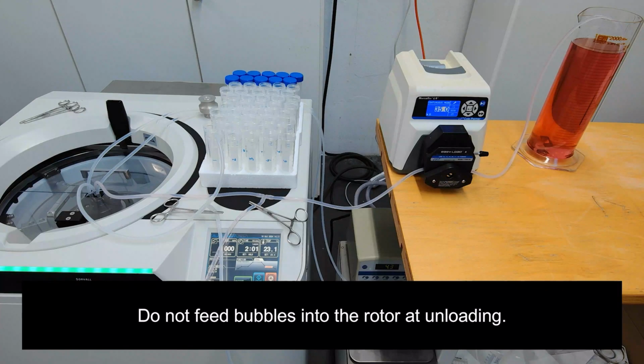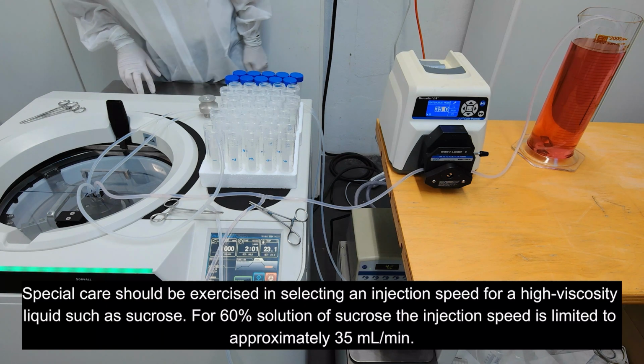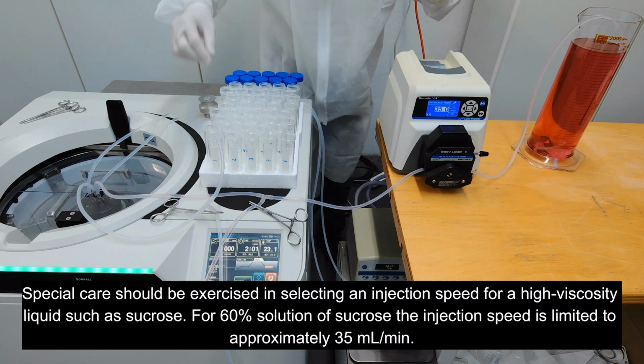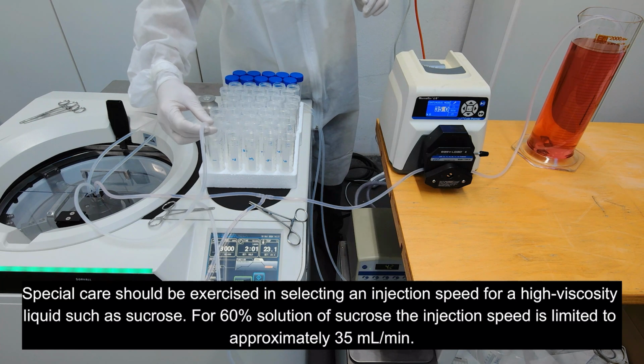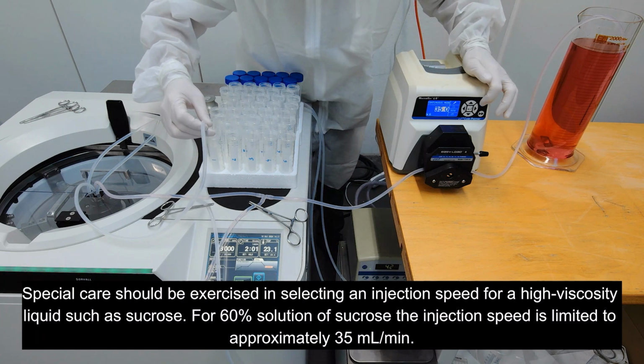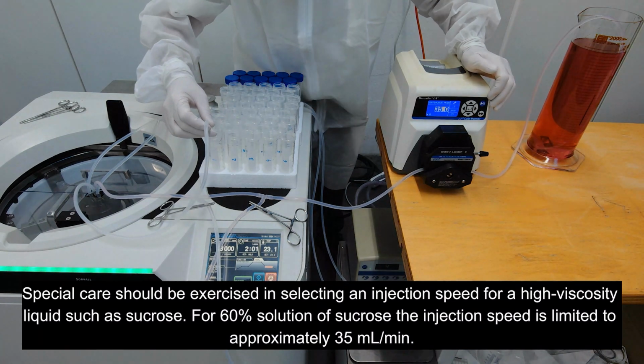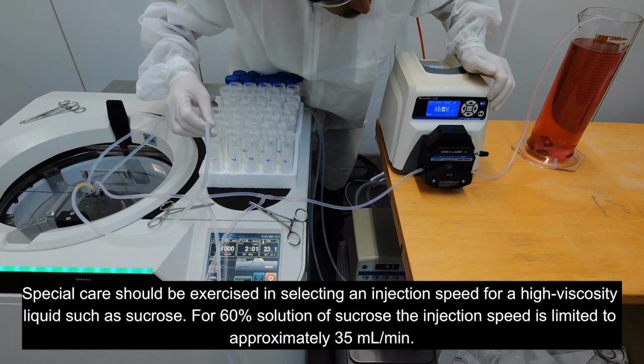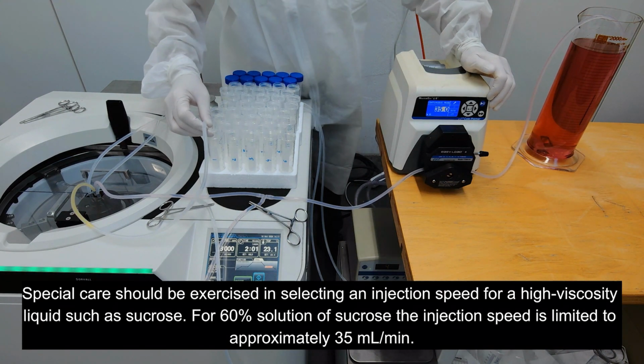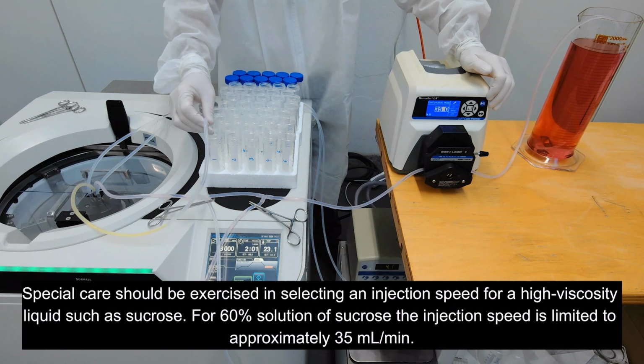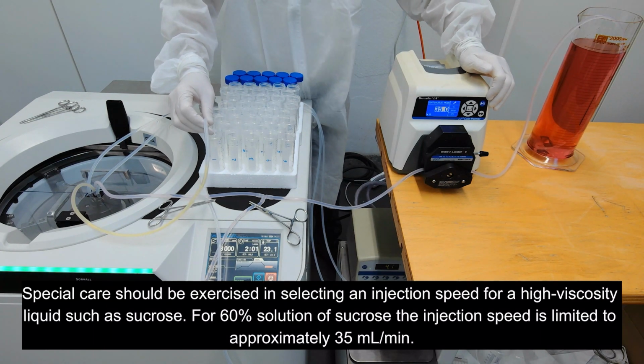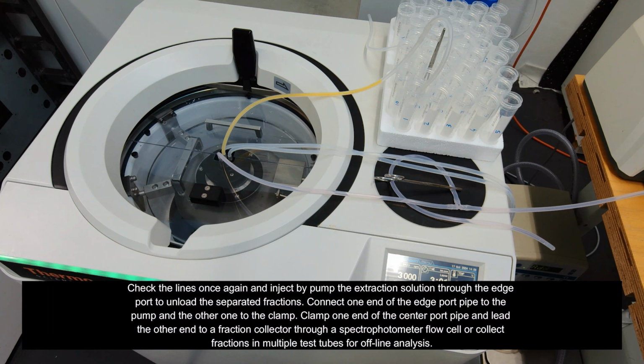Do not feed bubbles into the rotor at unloading. Special care should be exercised in selecting an injection speed for a high viscosity liquid such as sucrose. For 60% solution of sucrose, the injection speed is limited to approximately 35 ml per minute. Check the lines once again and inject by pump the extraction solution through the edge port to unload the separated fractions.